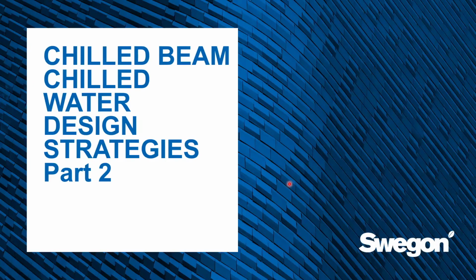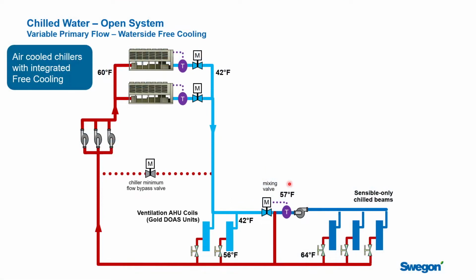This is part 2 of our chilled water design strategies for chill beam applications. In this series, we're going to talk about modifications to a typical chiller plant that are commonly done for chill beam applications. First one we're going to talk about is some form of waterside free cooling. Now, we have a situation here where we've got the chiller plant. We're showing you variable primary flow. This could be primary, secondary. It doesn't matter for the discussion.